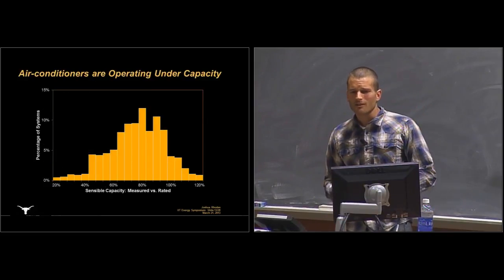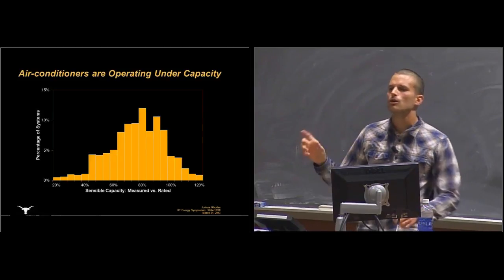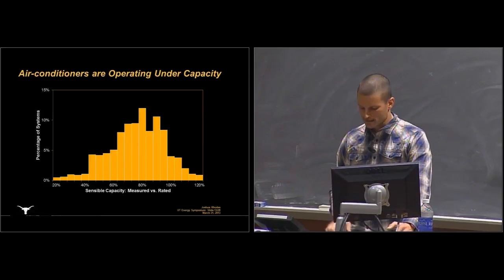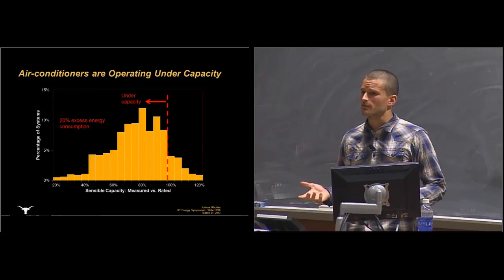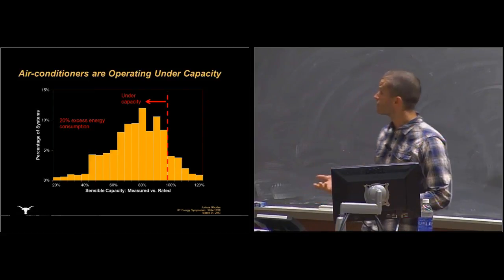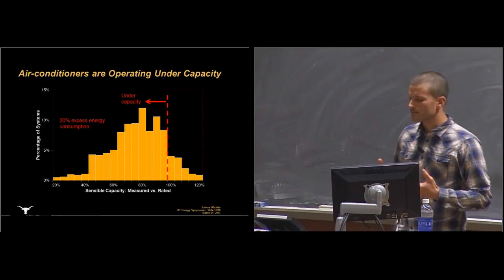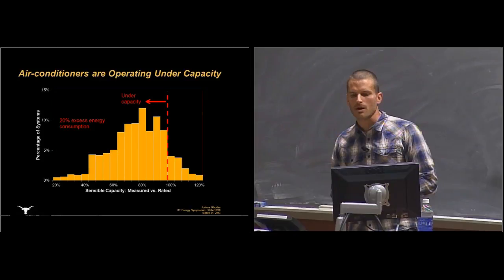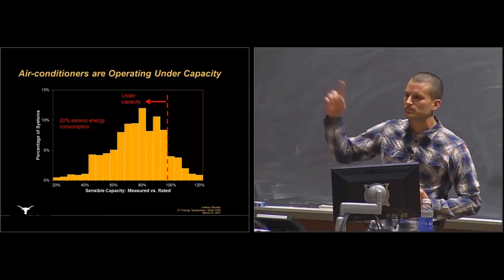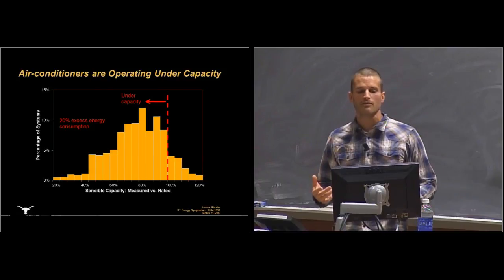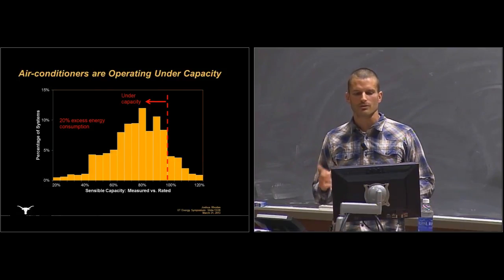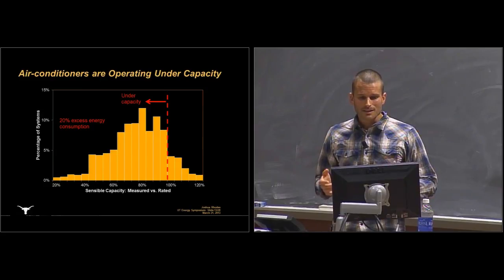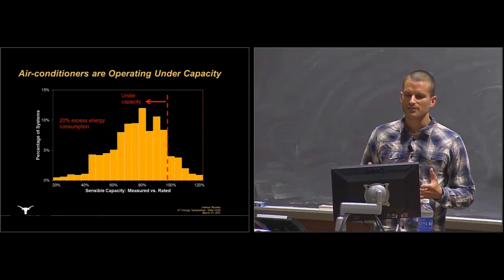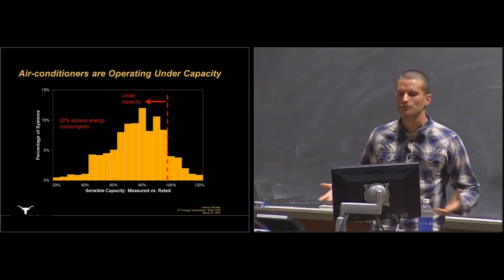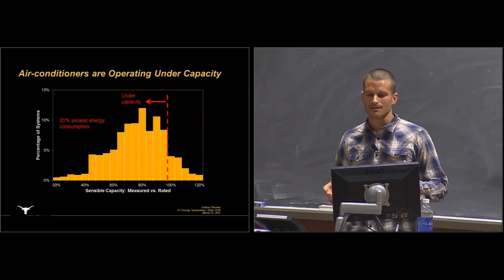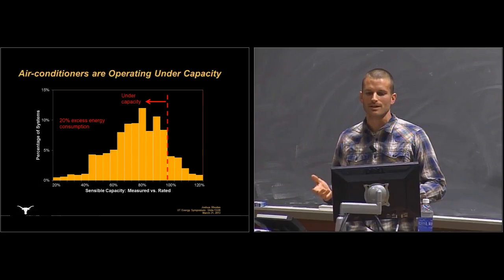Air conditioners are also operating under capacity. They measured how cold the air conditioner could actually get the air, and most units are operating under capacity, not performing to what they should. This could be from a host of things: an improper refrigerant charge, where the working fluid has leaked out and can't provide proper cooling, a fouled coil, or many other issues. These things just waste energy, using more than they should, and one visit from an HVAC consultant could really help a lot.